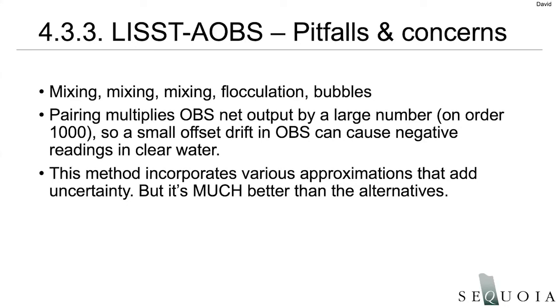But the only thing to keep in mind there is that this is the low end of the measurement range of this instrument combination. So if you need a highly sensitive measurement of low concentrations, this isn't the ideal instrument. This is designed to be hardy and to tolerate a wide range, including especially the upper range that you might find in rivers.